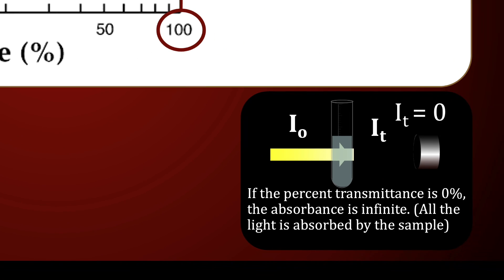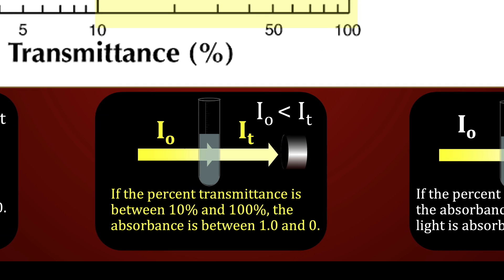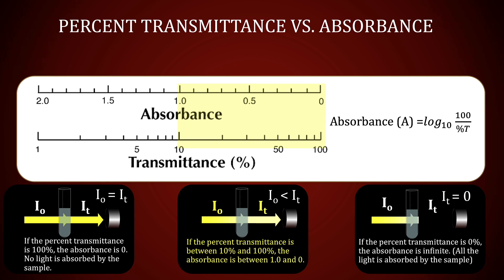If the percent transmittance is 0%, this means the sample absorbed virtually all of the light. Understandably, neither of these scenarios would be very useful from an analytical standpoint. Optimally, the absorbance should be between 0 and 1.0 to obtain the most accurate results.